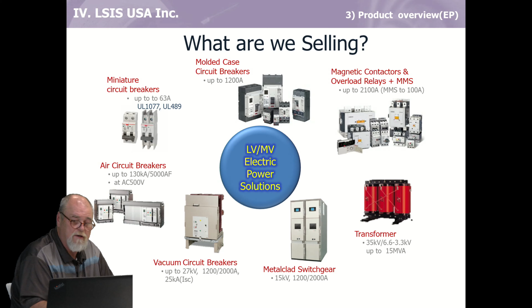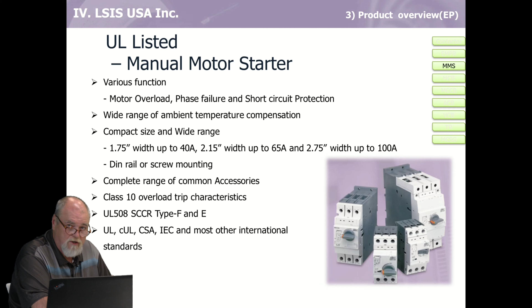Manual motor starters. This is an advantage for us in certain situations. We've actually tested our VFDs with the manual motor starters, so we can give you a series rating or coordination rating instead of having to use MCCBs or molded case circuit breakers and inline fuses to maintain 100K ratings. So it's a low-cost solution, simple product that can work with our VFDs. Again, it's an advantage of having our own test facilities.